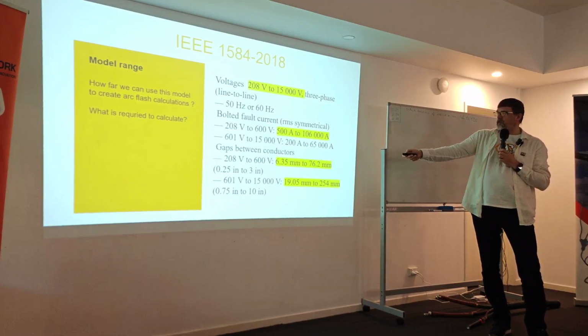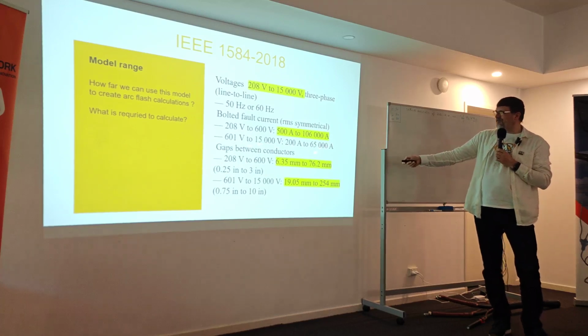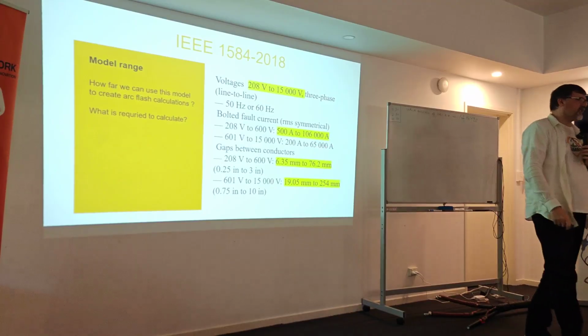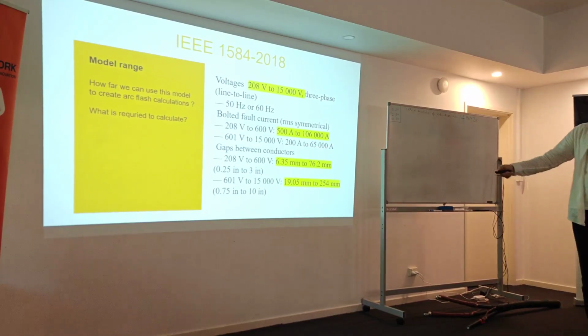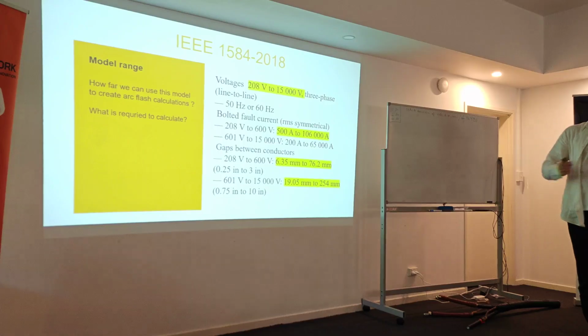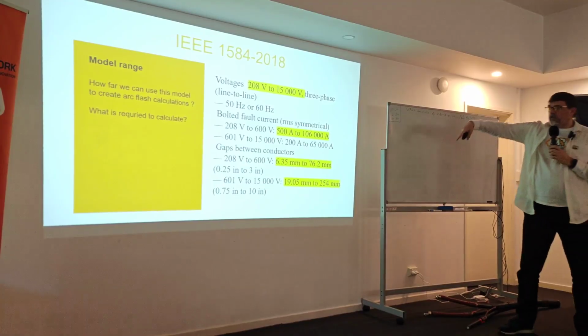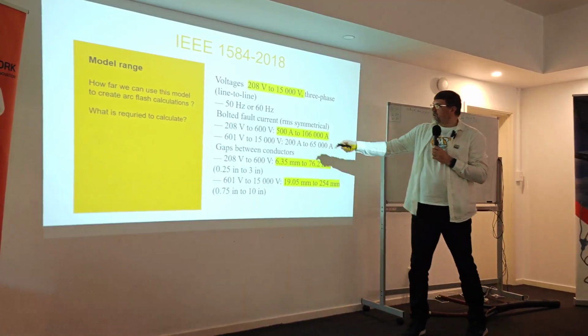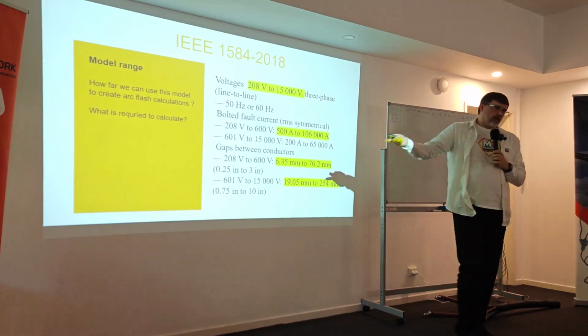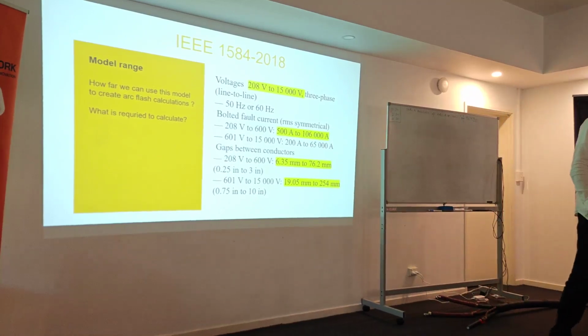500 amps, because of the voltage range, 500 to 106. And for medium voltage, 200 to 65, because you will not see this value for the 15 kV network, most of the time at least. For the gaps, which means the distance between the conductors, we start from 6 something to 76, and for the higher voltages, it's going up to 254 millimeters. So something like this, yeah. It's important to know because it also tells that below 208 volts you will not be able to use this model.